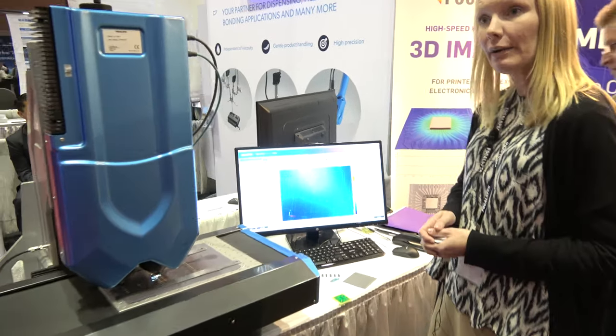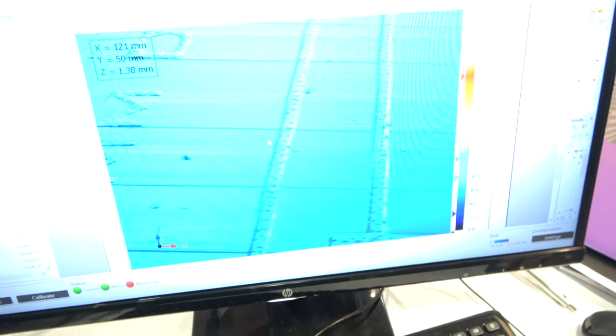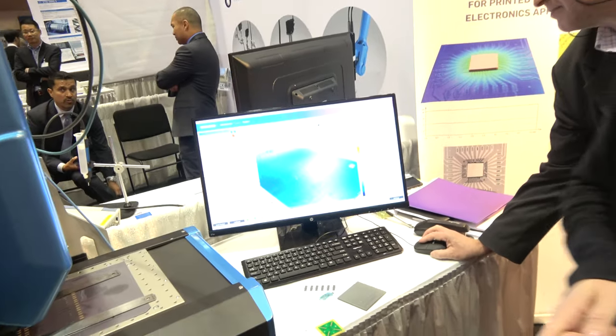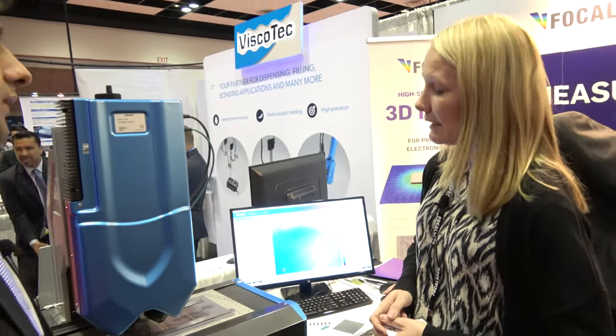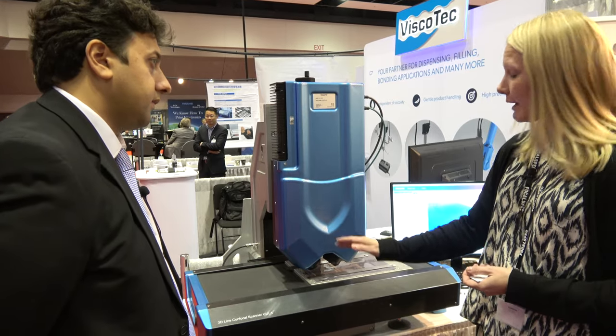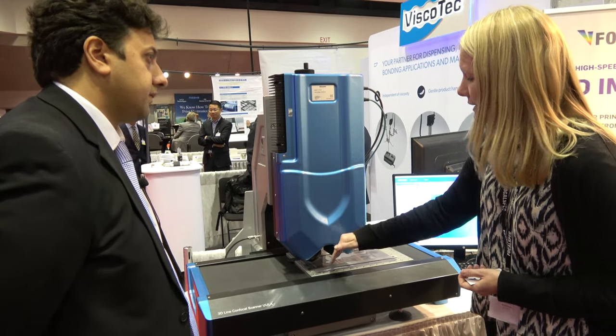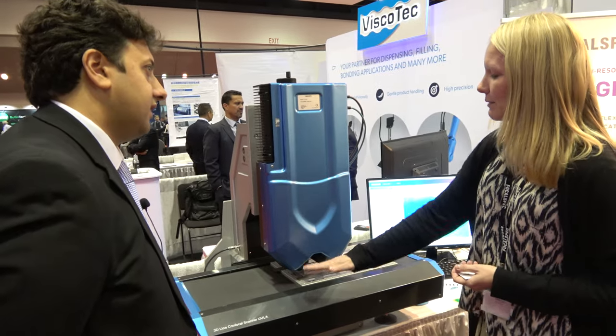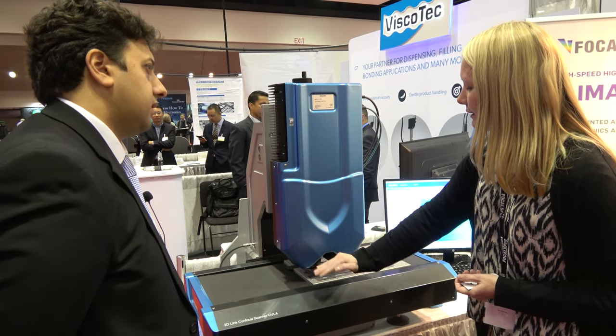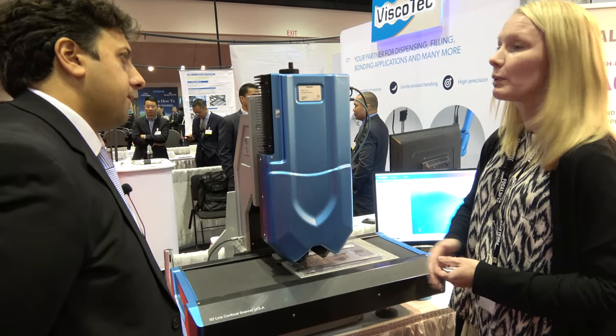And here we have the 3D profile now of the scanned area. How is it scanning the height? The technology — confocal line imaging — means that we are spreading the white light into all colors, all the wavelengths, and the wavelength or the color that is in focus with the surface is then measured back. And that means that we don't have to adjust the height, but the differences in form or shape of the topography come with one scan.